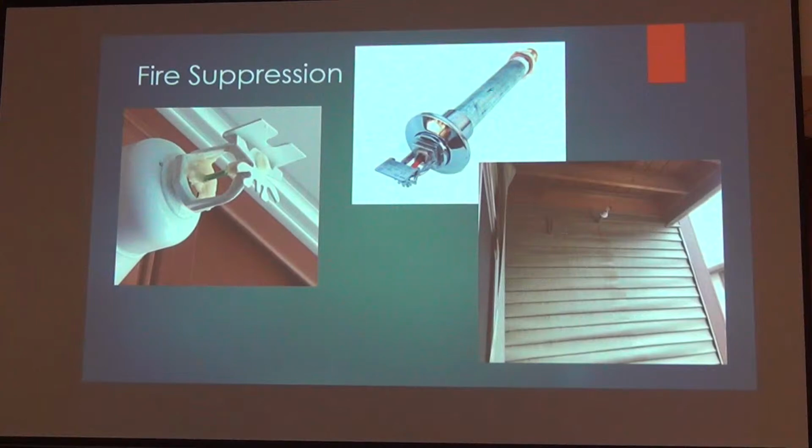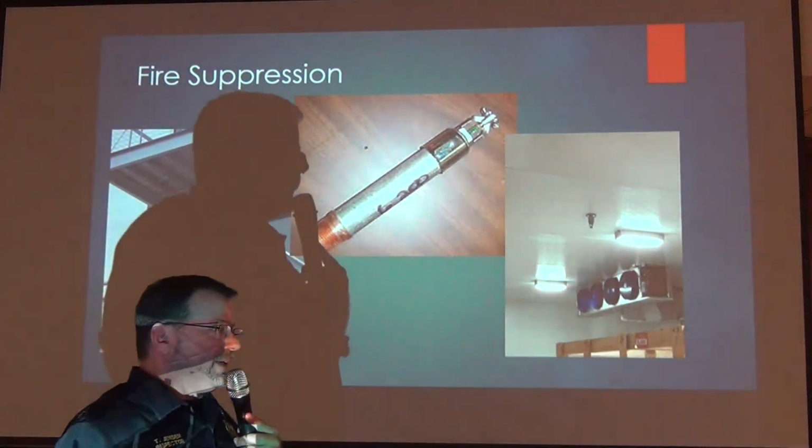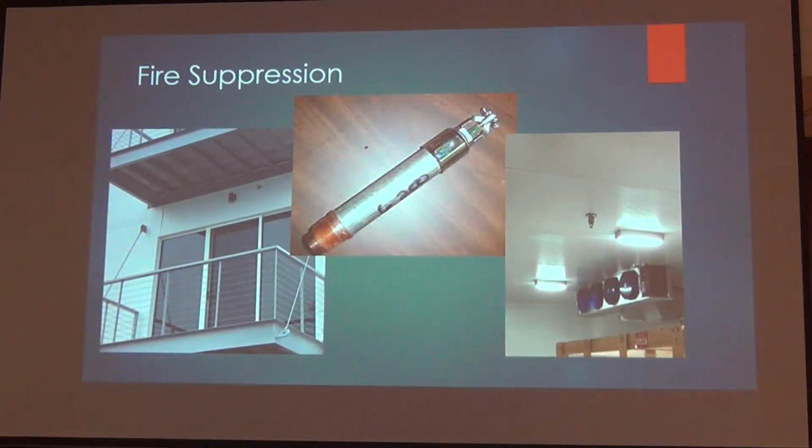When they do install these, and I probably should have put a picture in, this must go into the straight through of a T. Then they pipe into the side and put a plug on the top. Why? Because this is so deep it will obstruct the water flow otherwise. It cannot go into a 90. It has to go into the straight side of the T, not the branch side. You can feed the water to either side, but it must go into a T on the straight through, the run side.